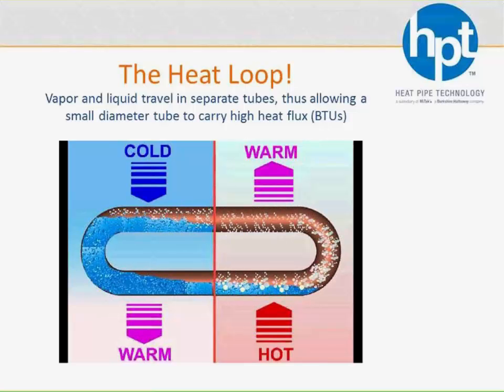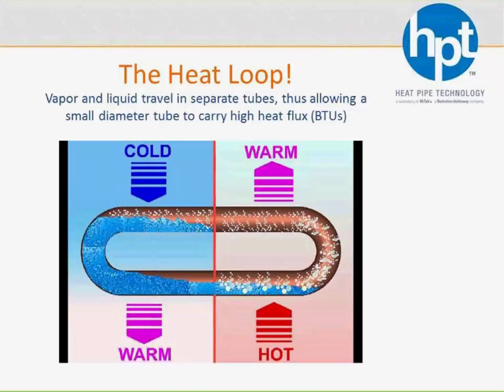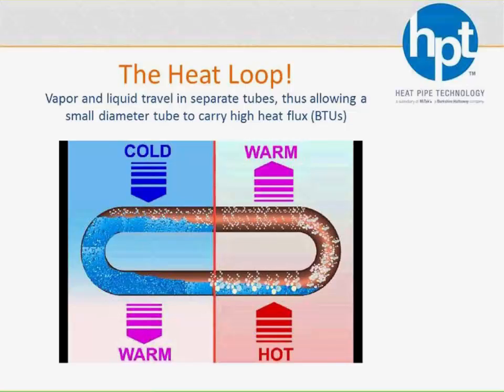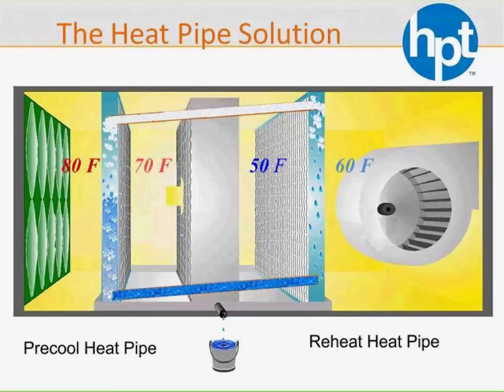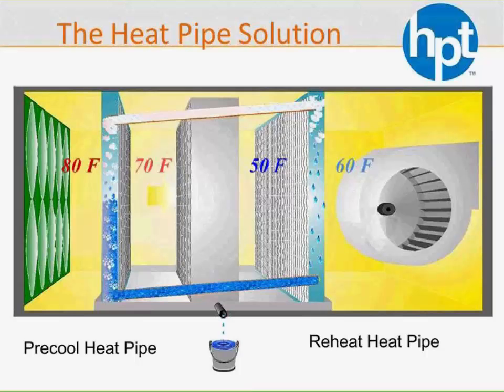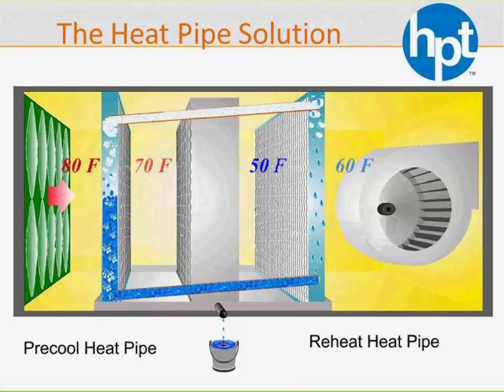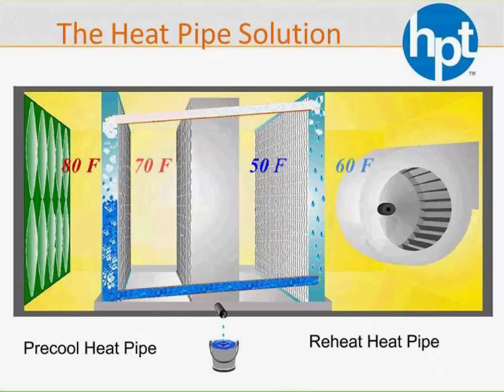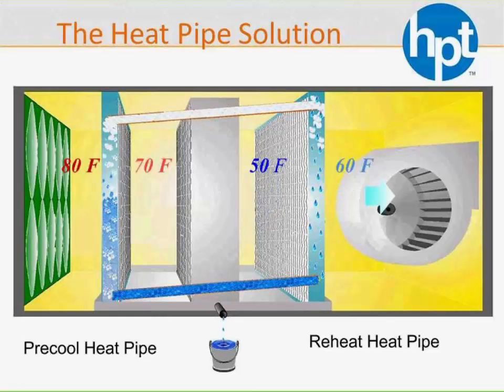And if it's energy recovery and the season changes and that hot outside air turns to cold outside air, then that refrigerant is just going to change directions all by itself, no tilting required, and just keep doing this loop type circuit as long as there's airflow and as long as there's a delta T. So for the wraparound heat pipe, we've taken it another step further, and instead of simply going in a loop from one airstream to the other, we're using it in a single airstream. And now when you've got this hot air coming in and the refrigerant picks up that heat and boils, instead of that refrigerant vapor going to another airstream and simply dumping off the heat, it's now wrapping around the cooling coil and we're using it as reheat.